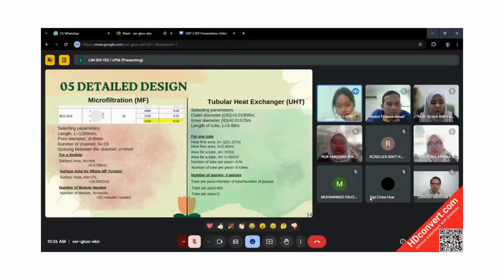So the area for one tube, we use pi multiplied with the outer diameter and length, and we get 0.29 meter square. To find the number of tubes, we divide both of them and we get 8 tubes. The number of passes we set as 4 passes because the more the passes, the more the energy transfer in the tubular heat exchanger. So we just divide the 8 tubes by 4 passes and we get 2 tubes per pass.